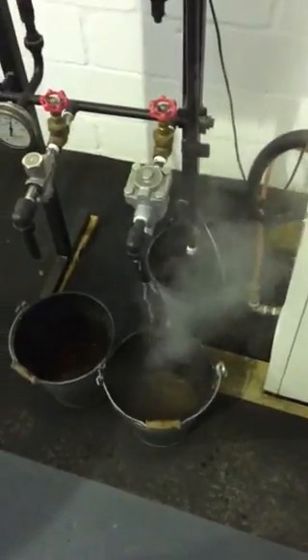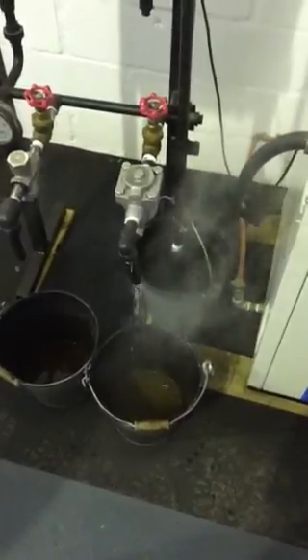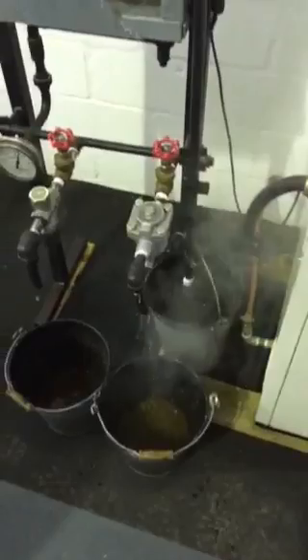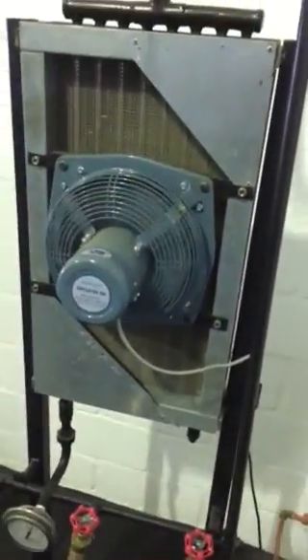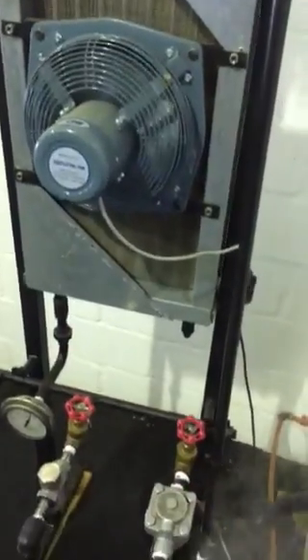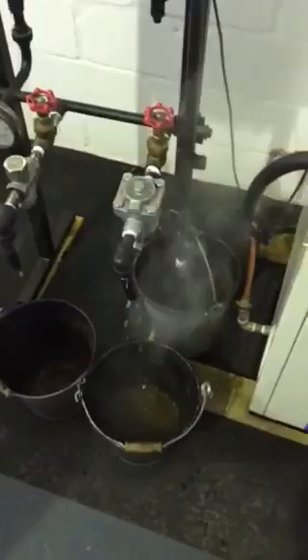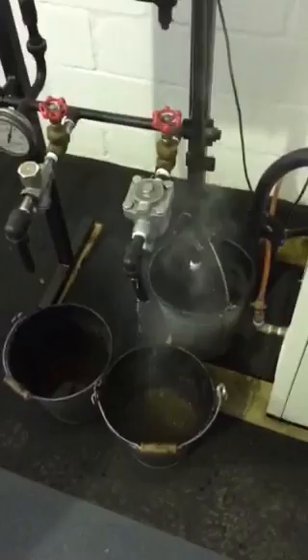This is a comparative test between a free float steam trap and a Venturi orifice steam trap. You can see the fan going on the heater battery — it's operating and discharging with pretty steady opening and closing.